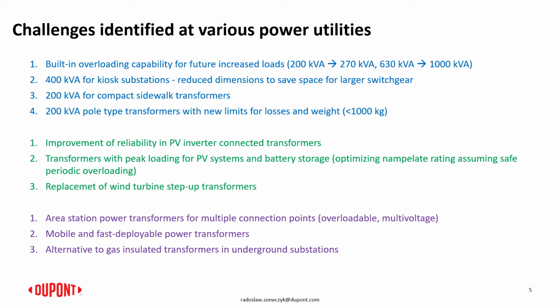1000 kVA. We see the situations where the kiosk substations, the compact kiosk substations in the urban areas, must provide more space for the larger switchgear or for more connections to be made, and the transformer must be made more compact to accommodate for that. We can see some developments for the compact sidewalk transformers, which are needed in the larger numbers in the city areas. So we see those requirements in the distribution transformers.